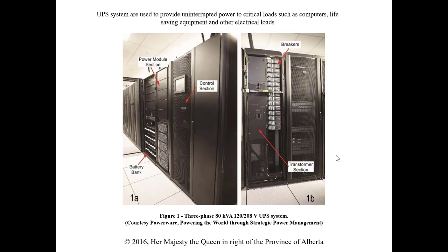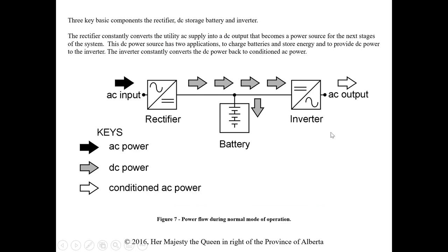Here is an example of a large UPS system. If you're only used to seeing a simple computer backup, it's just something you plug into the wall, but the one in the college would be significantly larger. We have breakers, a transformer section, a power section, a battery bank, and a control section. The operation of a UPS has three components: the rectifier, the battery, and the inverter section.